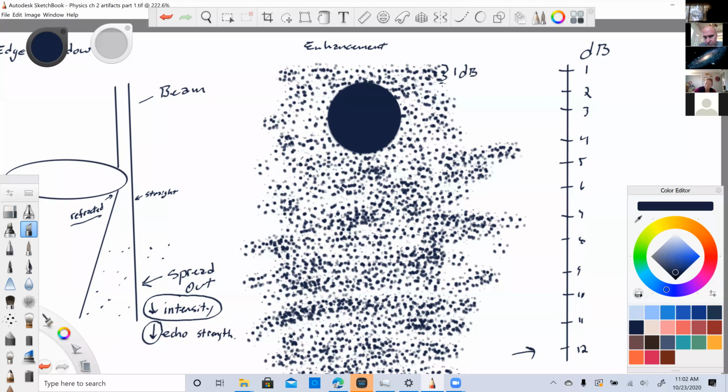And I'll go ahead and give it the 2 decibels. 2 decibels here. And then guess what? I didn't do that perfectly well, but I think you get the idea. There is a 0, or darn near close to it, 0 decibel loss there. So we're expecting, let's just say 3, 4, 5. We were expecting all those decibels to be lost, and then they weren't lost.